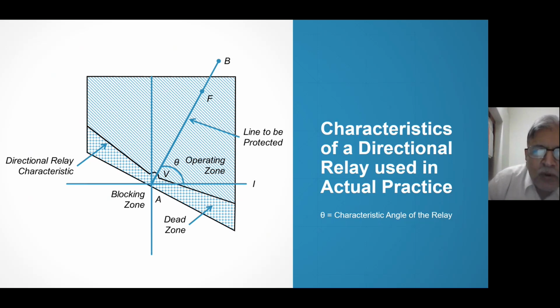Try to understand. Therefore this minimum voltage will be there, and this minimum voltage at different angles is different, and for that minimum voltage you have to draw a point, and join all points. This is the characteristic of the relay. This is the characteristic of directional relay. Beyond that characteristic on this side is operating zone, and below the zero torque line is blocking zone.